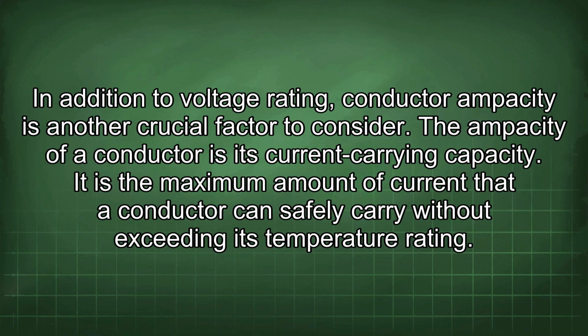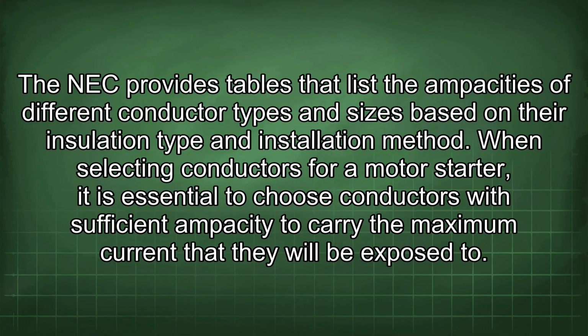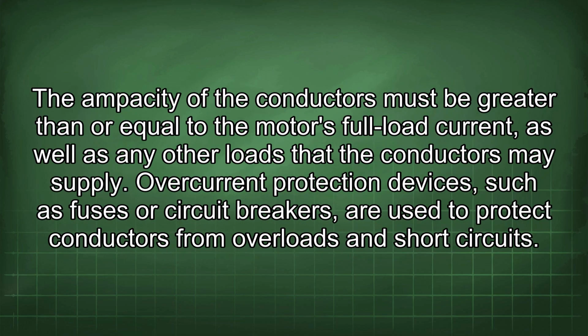In addition to voltage rating, conductor ampacity is another crucial factor to consider. The ampacity of a conductor is its current carrying capacity. It is the maximum amount of current that a conductor can safely carry without exceeding its temperature rating. The NEC provides tables that list the ampacities of different conductor types and sizes based on their insulation type and installation method. When selecting conductors for a motor starter, it is essential to choose conductors with sufficient ampacity to carry the maximum current that they will be exposed to. The ampacity of the conductors must be greater than or equal to the motor's full load current, as well as any other loads that the conductors may supply.